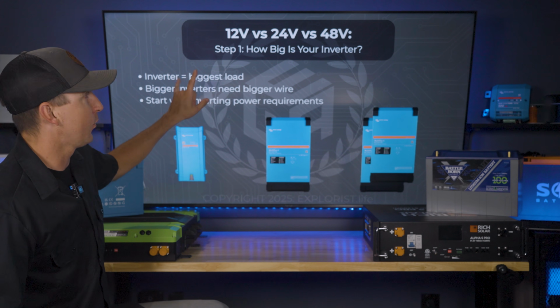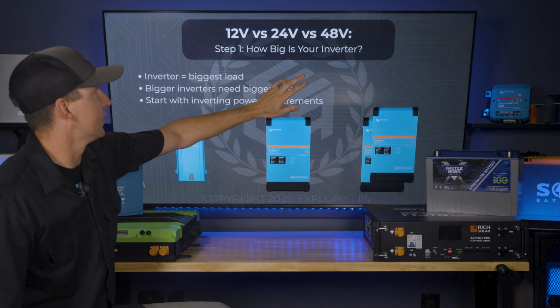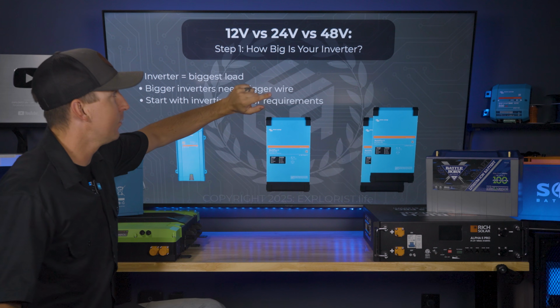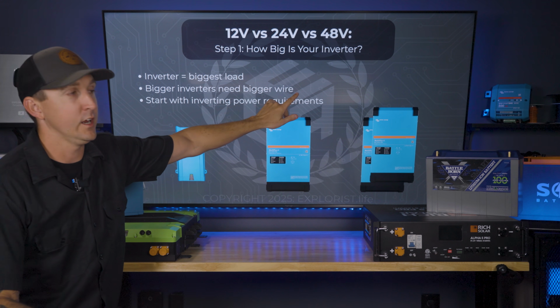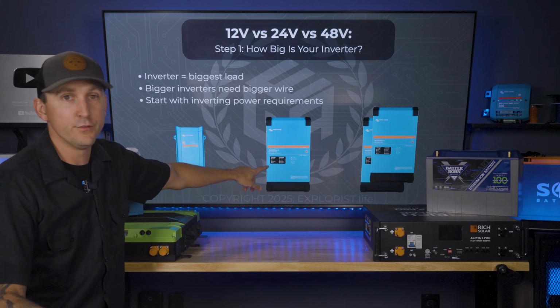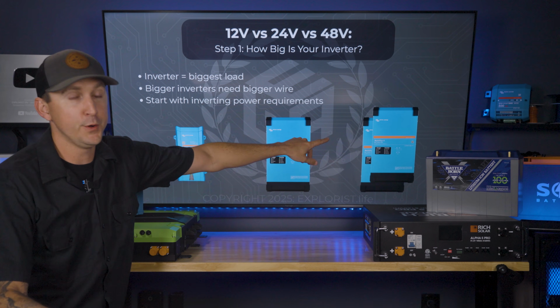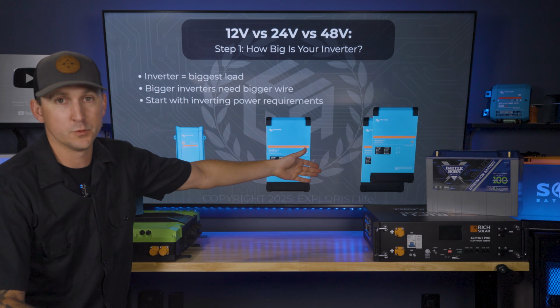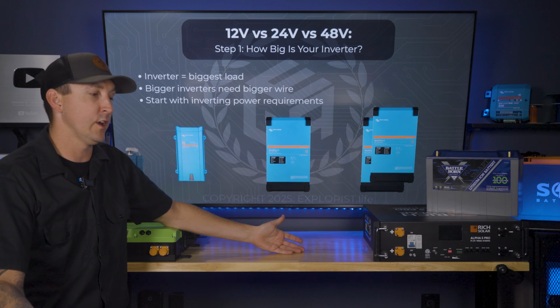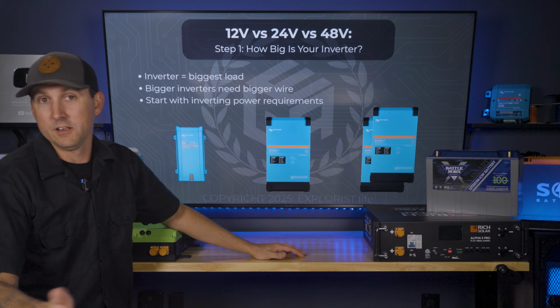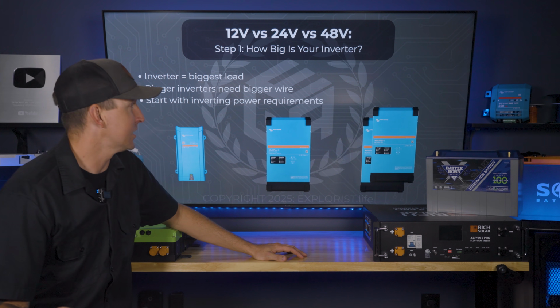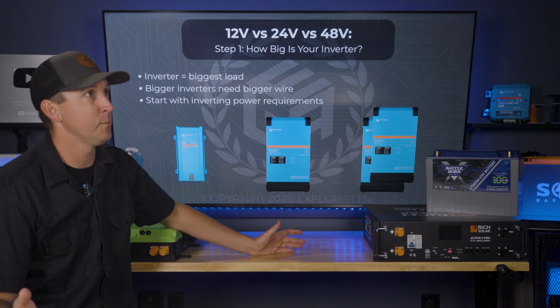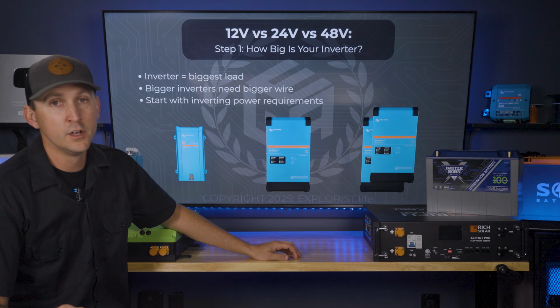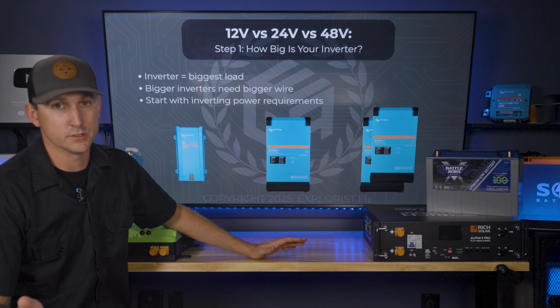So I always start with: how big is your inverter? More specifically, how big is your overall inverting needs? Maybe you've got one inverter, or maybe you've got 2 inverters. If you've got 2 3,000 watt inverters, then your overall inverting capacity is 6,000 watts, you just add those together. And that's realistically going to be the main determining factor of 99% of electrical systems.